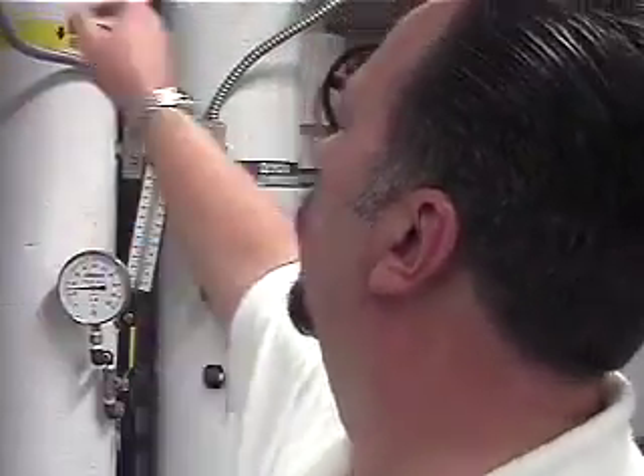So this is heat exchanger 2. This is your hot water heat exchanger, so this serves the hot water coil on this air handler. And this is the modulating valve for it. Off of pump 7 or 8, you'll circulate through here on the load side. This is on the primary side, so this is coming off of the loop with 5 and 6. We'll modulate this to maintain your discharge air temp on your air handler.